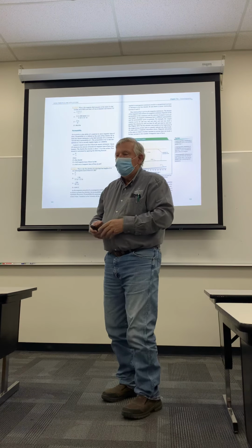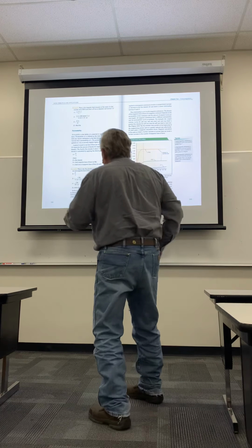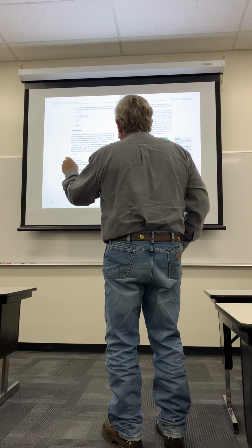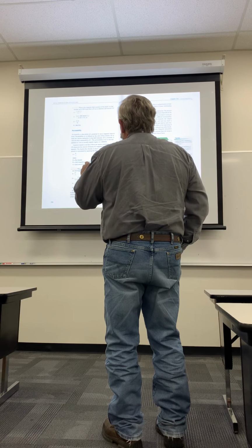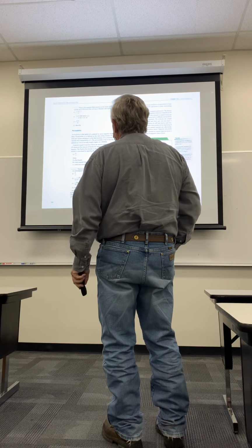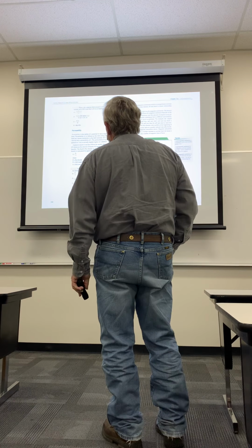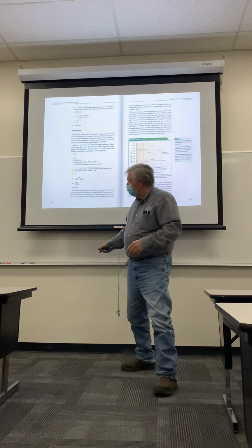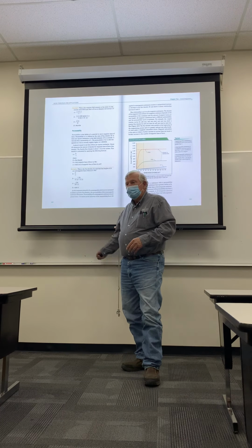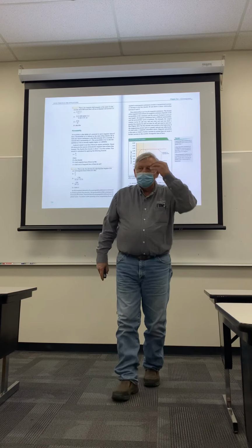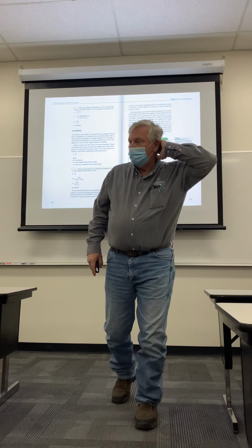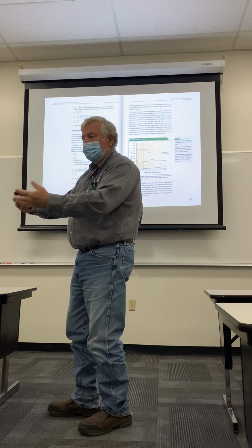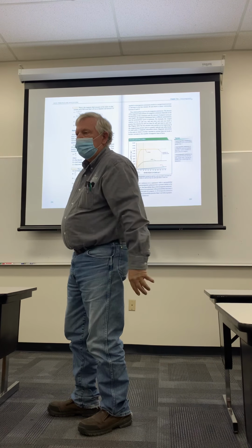So a good thing to have is a gauss meter. If you see right here, a gauss is equal to 1 line of force per square centimeter. Gauss, which is abbreviated capital G, measures the density of magnetic lines of force. So you can take a gauss meter and walk up to an assembly line or a piece of equipment or a pipeline, a pipe that's carrying something, and use that gauss meter to see how magnetic it is.